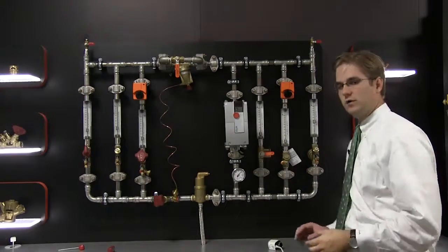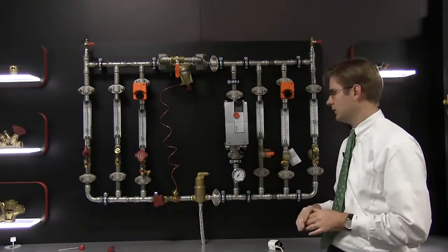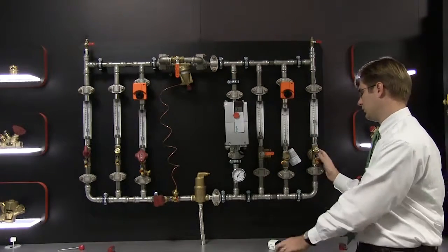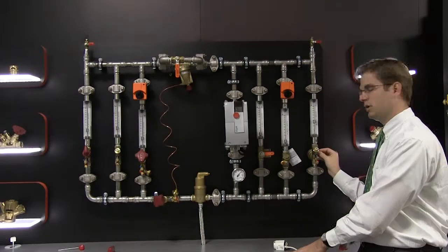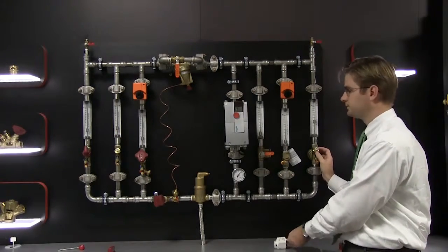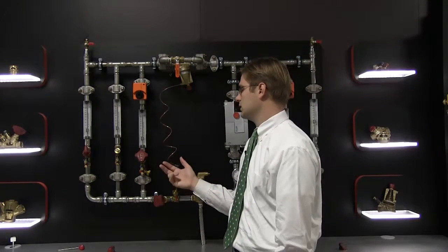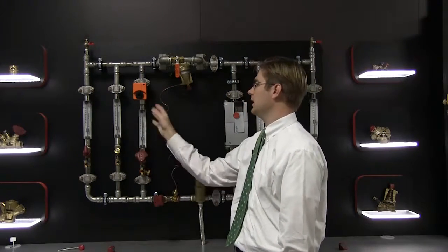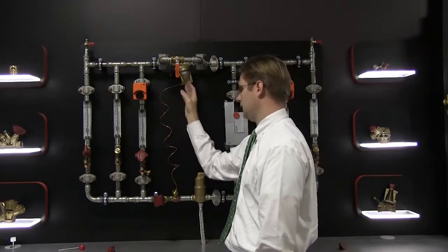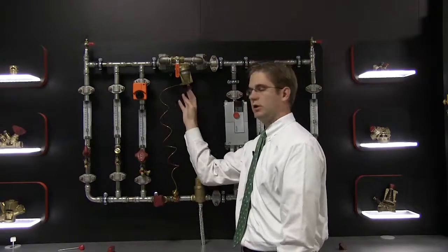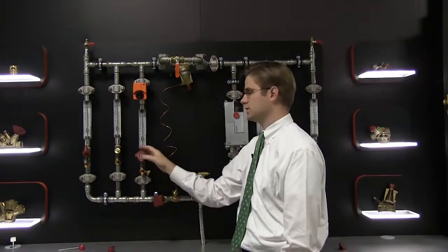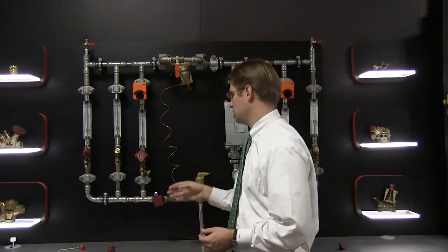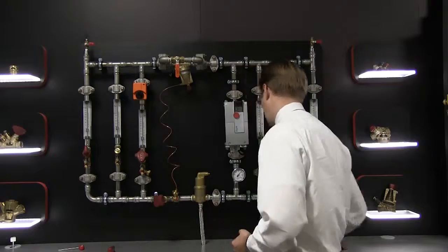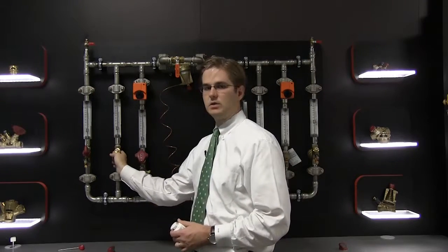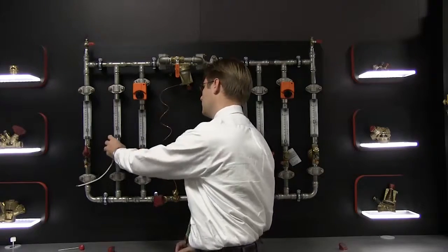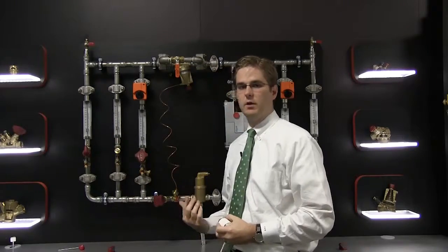So your 3 different options for achieving pressure independence. First is an all-in-one valve, which combines a differential pressure controller, a manual balancing valve, and a control valve all in one. Your second option is to use a standard manual balancing valve and a modulating control valve with a differential pressure control valve. This differential pressure control valve can be used on multiple terminals, not just 3. And your third option would be to use a differential pressure control valve with our new balancing and control valve, our TBV CM line. So any option that you want, we have a way to achieve pressure independence.